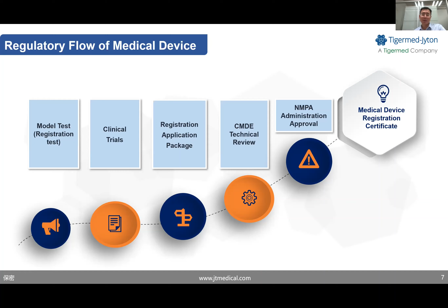And with the trial results plus the testing report plus the R&D work and laboratory validation data and process data, quality control data, stability data, everything together is compiled into a package, then you submit it to the authority. CMDE or the Provincial Medical Device Review Center will do the technical review. And later, if the technical review is positive, the NMPA administration department will do the final approval. For class 3 devices, the technical review result is very important. In general, this conclusion will decide the final result, yes or no, to approve it.